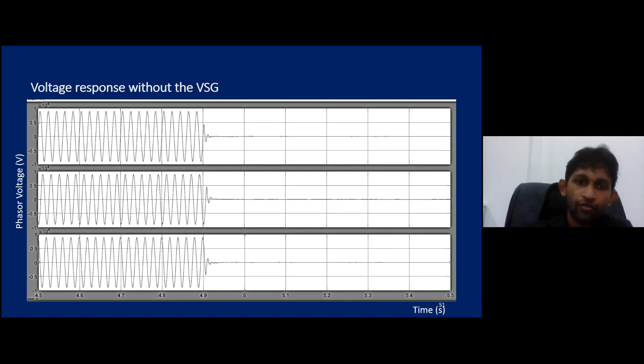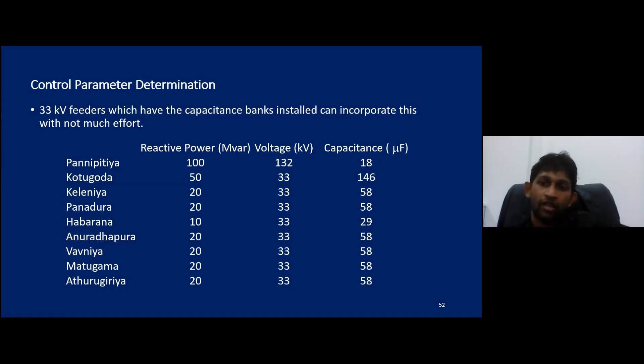We know that installing at 11 kV would be a problem because we'd need capacitor banks, inductors, and so on. But these places have already installed VAR compensators and capacitor banks. Can we use these for the mentioned method? Yes, we simulated them on the 33 kV feeder, using a 33 kV, 20 Mvar capacitor bank as the filter, and we got a good result.